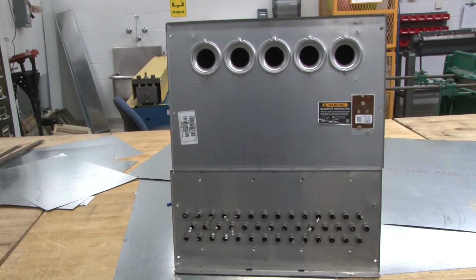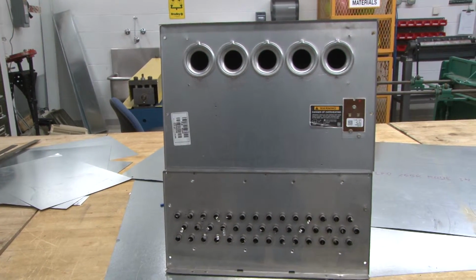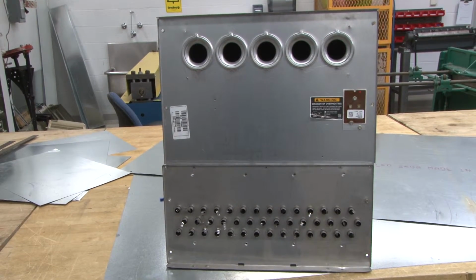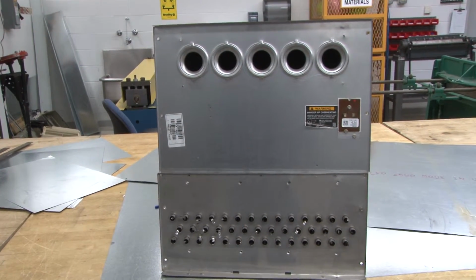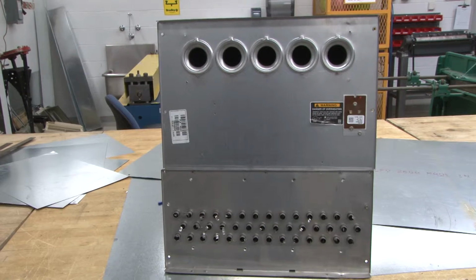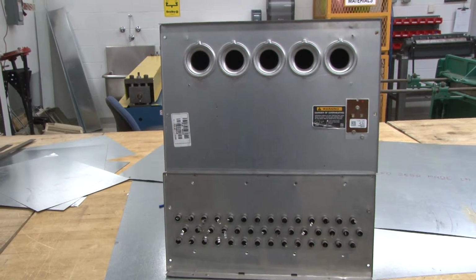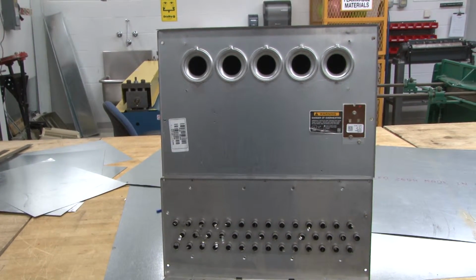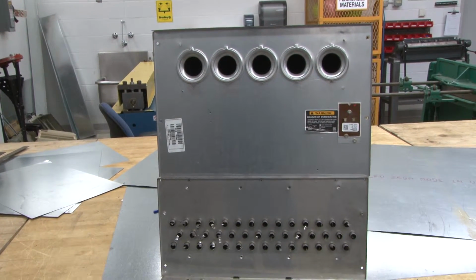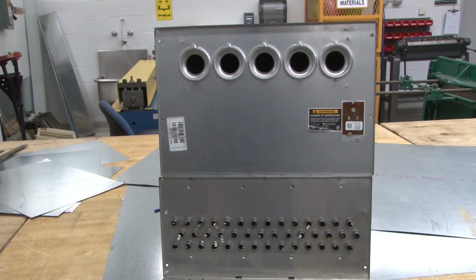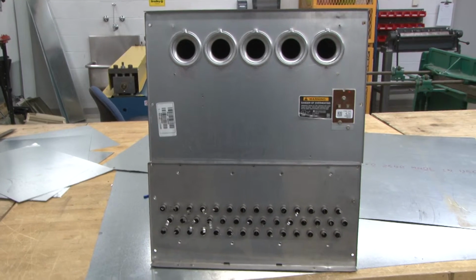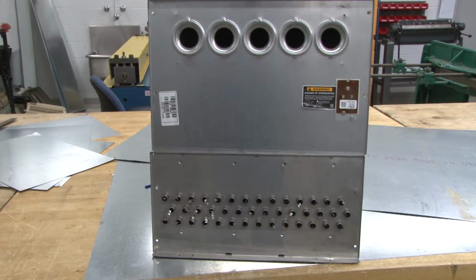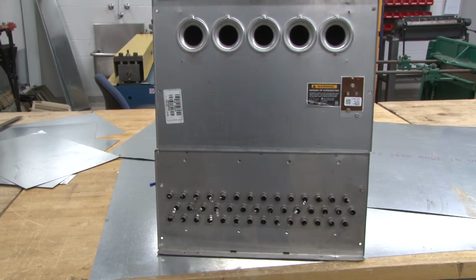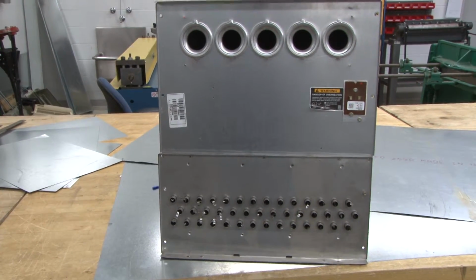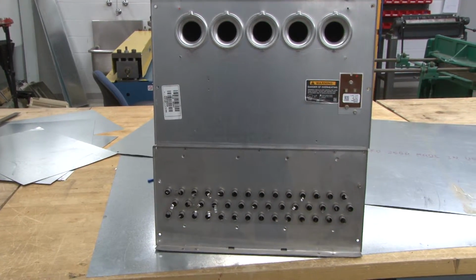In this video, we're going to discuss a heat exchanger of a 90% efficiency furnace. What you see in front of you is the front of a heat exchanger, where you see the intake ports of the heat exchanger at the very top, where you see the 5 openings. At the bottom of the front is the secondary heat exchanger, where you see the ports for the inlet and exiting of the flue gases and condensate.